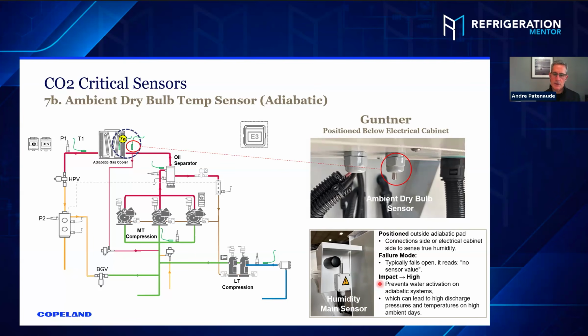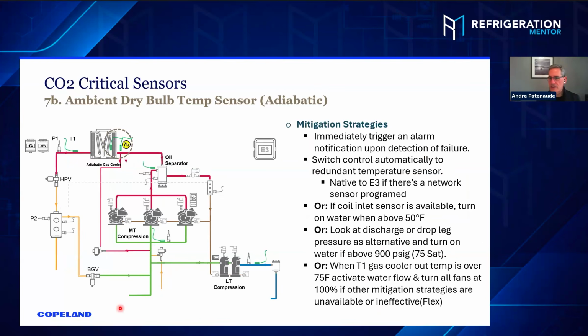Might not be a problem in the winter, but if you're at peak 4 p.m. and it's 95 degrees outside, it's going to be a problem, which can lead to high discharge pressures and high temperatures in high ambient. And of course, if the gas cooler is sized for water flow on the hottest day and you don't have water flow, you're going to go off on high head. So that's the danger of any system that loses its water flow, because those gas coolers are not designed to operate dry at the highest anticipated ambient. They're designed to have water flow in order to meet that capacity. That's how they can keep the coils smaller.